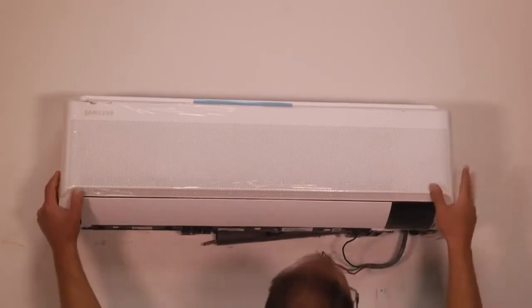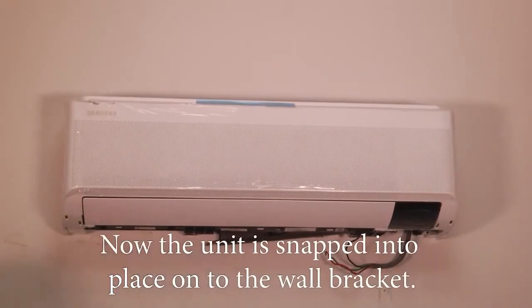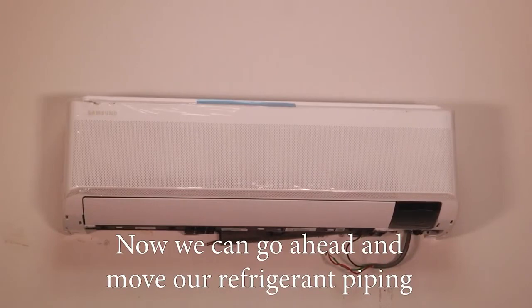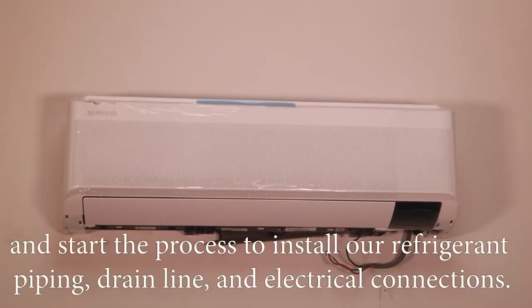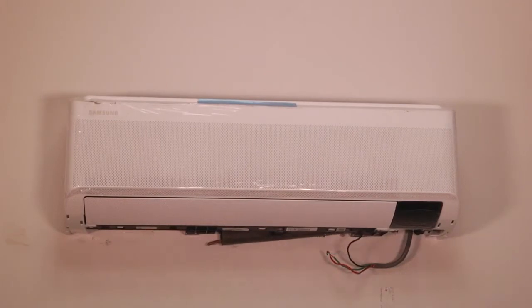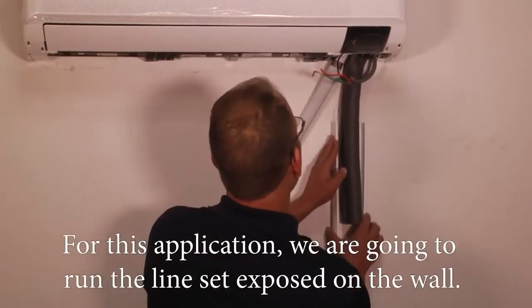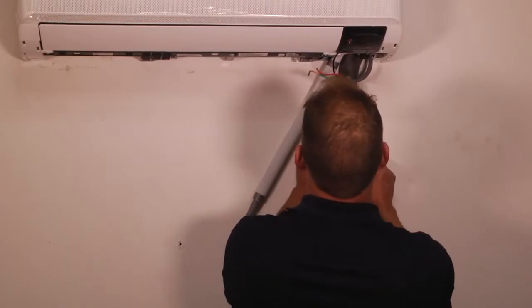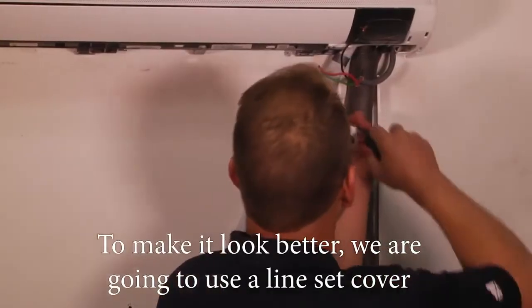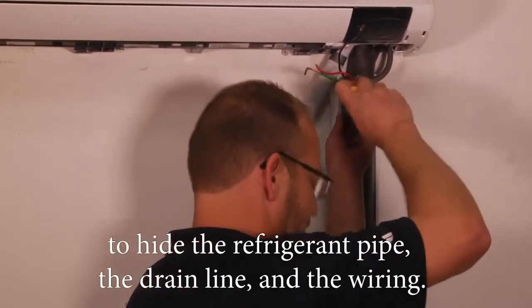Now the unit snapped into place onto the wall bracket. Now we can go ahead and start the process to install our refrigerant piping, drain line, and electrical connections. For this application, we're going to run the line set exposed on the wall. But to make it look better, we're going to use a line set cover to hide the refrigerant pipe and the drain line and the wiring.